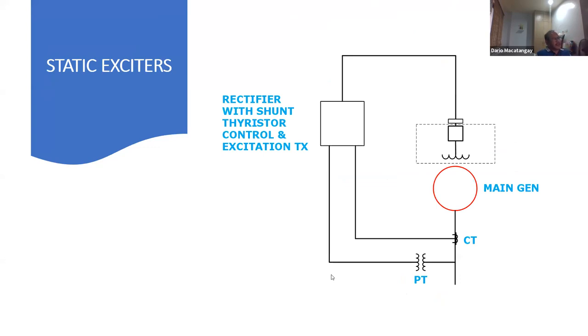This one is a static type. As you can see, power is derived from the CT and PT, from the generator output. It has its own thyristor control and excitation transformer and is fed to the rotating field. That's the static exciter, okay? So it's already 4:23, so we need to move a little bit faster, okay?